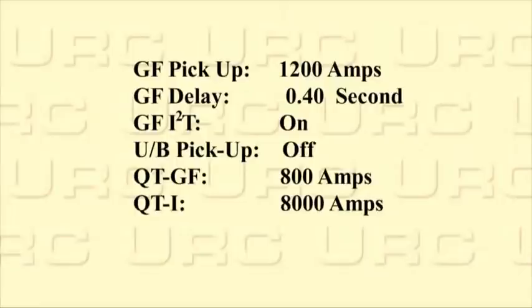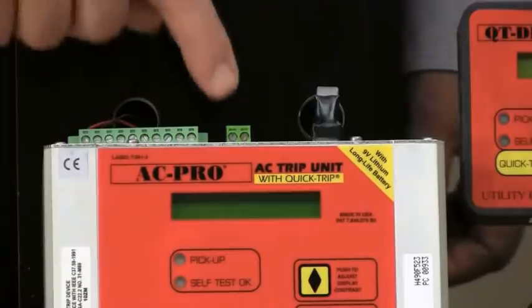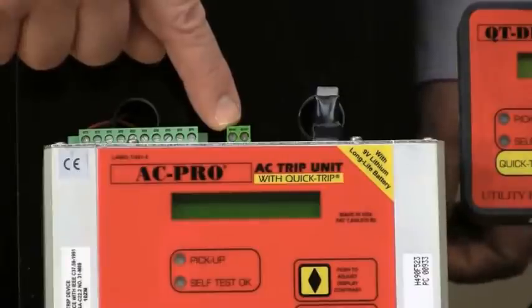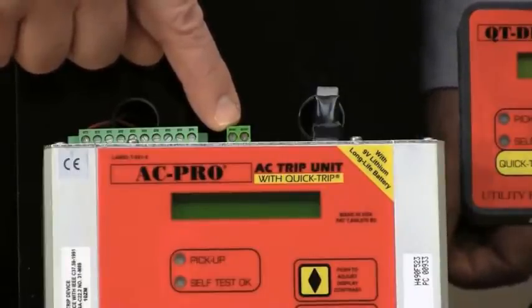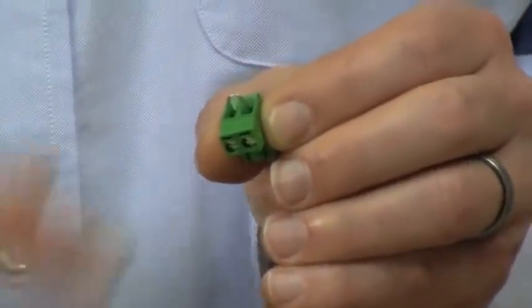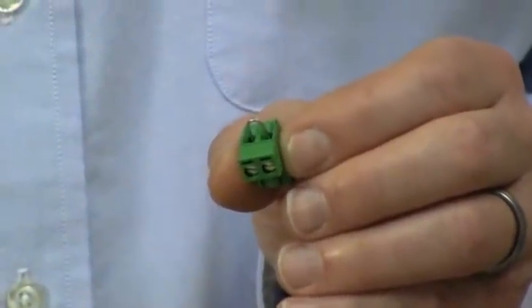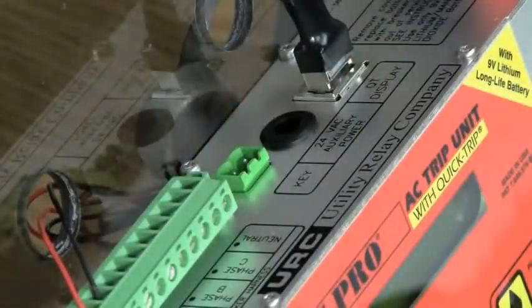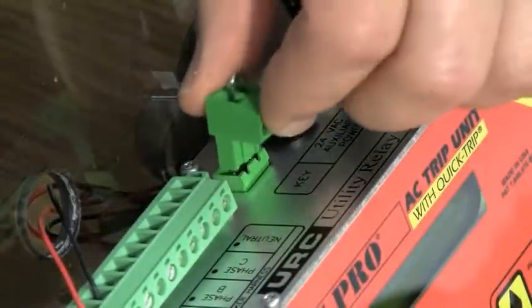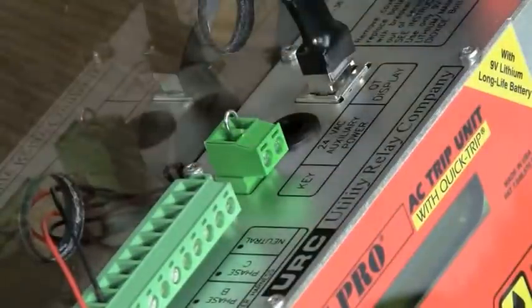Looking at these settings, you'll notice that they're all either in amps or in seconds — no calculations are required to convert the settings. The key is a security feature and limits access to the settings; only somebody familiar with the ACPro can enter or change the settings. The key is just a short piece of jumper wire placed in this two-pole terminal block — a paper clip works just fine. Insert the two-pole terminal block with the key jumper wire into its mating receptacle. The key is now in place.